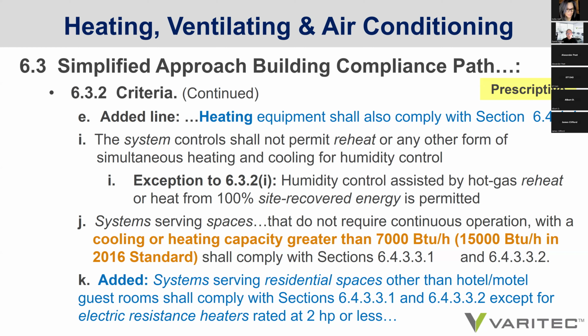Line E on 6.3.2 criteria has added language on heating equipment, stating that it shall also comply with section 6.4.1.4. System controls shall not permit reheat or any other form of simultaneous heating and cooling for humidity control, with the exception that humidity control assisted by hot gas reheat or heat from 100% site recovered energy is permitted. Systems serving spaces that do not require continuous operation with a cooling or heating capacity greater than 7,000 BTUs per hour shall comply with sections 6.4.3, etc. Be aware that in comparison to the 2016 standard, that's over a 50% reduction in the BTU level. So that's considerable. Systems serving residential spaces other than hotel or motel guest rooms shall comply with their own sections.